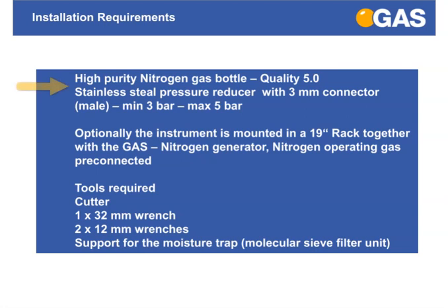We need high purity nitrogen, either a gas bottle with a stainless steel pressure reducer, or optionally you can order the instrument mounted in a 19-inch rack together with the gas nitrogen generator. The following tools are required: a cutter and 3 types of wrenches, as well as a support for the moisture trap.